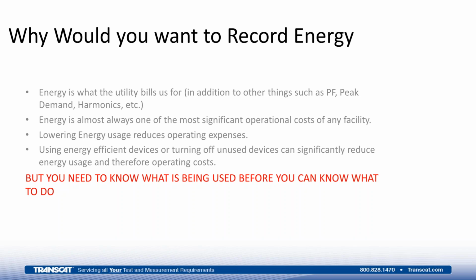This wasn't as simple as just having a contractor come in and replace the lighting with what they called more energy efficient lighting. The particular group, that department, had to document the usage and the reduction, and they also wanted to prove that, in fact, the lighting was saving the amount they wanted. So they wound up having to do a 30-day recording before doing any relamping, measure the energy usage on the lighting loads, have the company come in and do the relamping, and then do another 30-day recording to see just what they were able to attain after relamping.